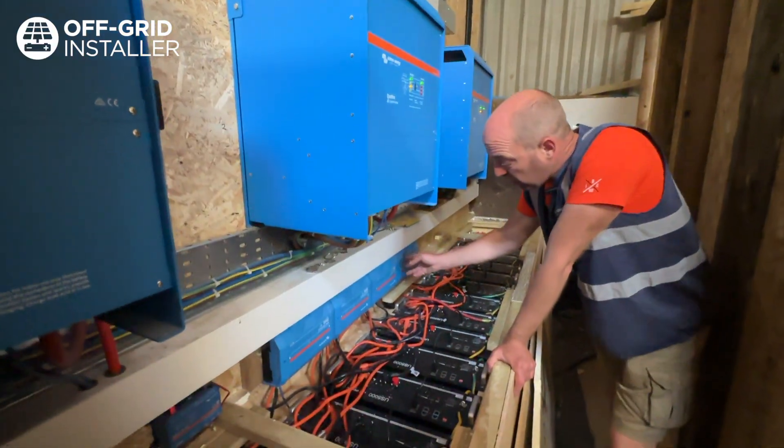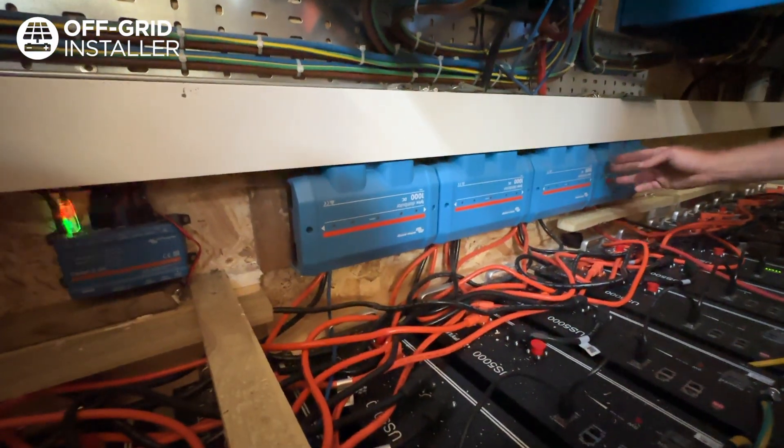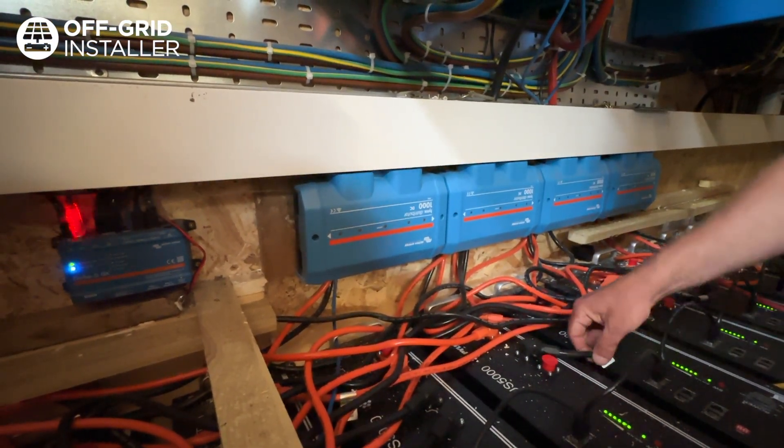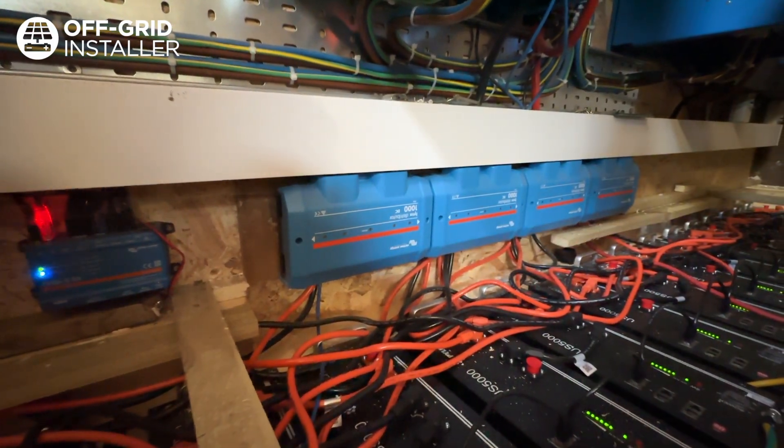Here we've got four Lynx Distributors — basically negative and positive bus bars running through, so all your mega fuses are in there. The mega fuse is off every two sets of batteries. You can see there are two, so they will each go back to a 125 amp fuse.